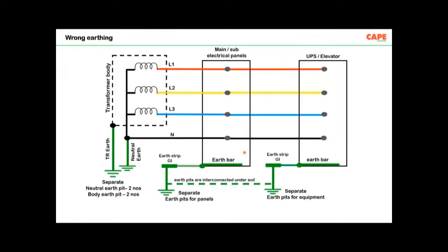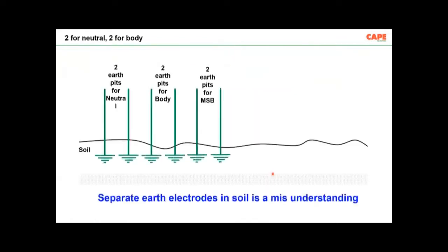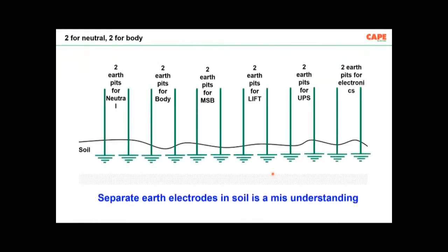Now, but what do we do actually? In most installations in India, the transformer neutral has two connections to two earth pits in soil. Transformer body, two separate. Panel board, two separate. UPS, two separate. Elevator, two separate. So this is basically an undefined network. This is what we do: separate earth pits. So basically, this is an undefined earthing.